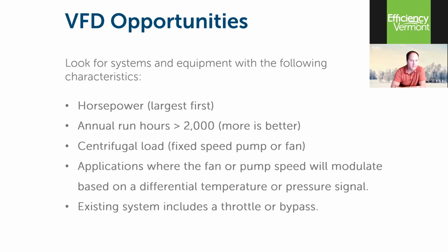Just more on the opportunities. You know, you walk into a lot of different stuff every day. As one of my mechanical contractor friends says all the time, is the juice worth the squeeze? That's the question we're asking ourselves all the time. That's a half horsepower fractional horsepower pump. Yeah, I could put a VFD on it, but it's only going to save $10 a year. Moving on. So we look for a high horsepower first, whether it's in HVAC, whether it's in a water system, a wastewater system, process manufacturing. Start with your highest horsepower.